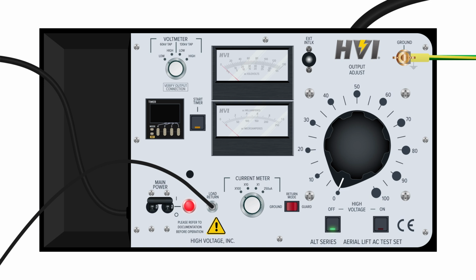Recheck your connections and that there is sufficient distance between the DUT, the high voltage section, and the main control panel, as well as 3 feet of distance between the cables and any grounded objects.